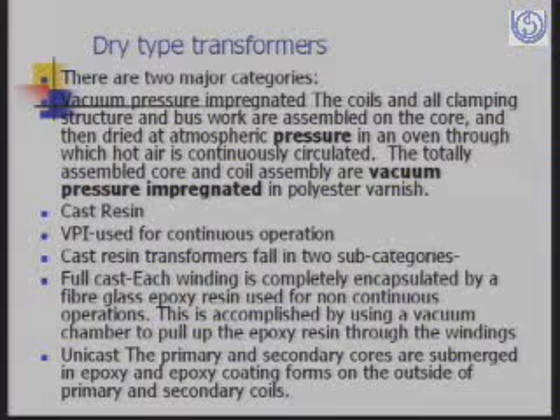In the unicast type of transformer, the primary and secondary coils are submerged in epoxy, and an epoxy coating forms on the outside of the primary and secondary coils. The epoxy resin is not forced through the winding, so it is not as solid as the full cast transformer.